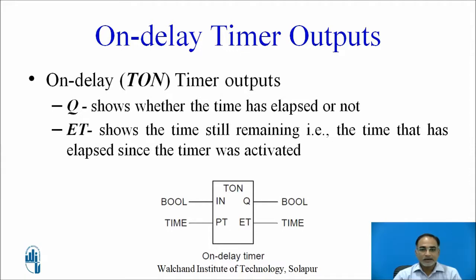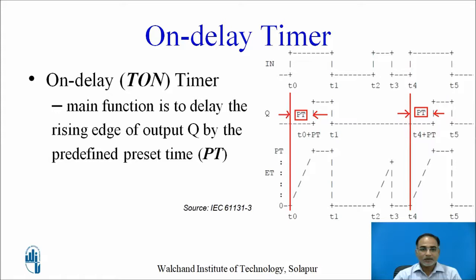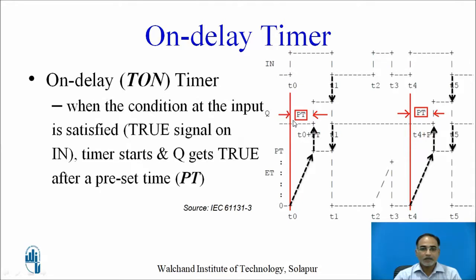The main function of the on-delay timer, also known as TON, is to delay the rising edge of Q by the predefined preset time. At t0, when the input changes from 0 to 1, the timer starts immediately and the ET value increments toward PT. When ET equals PT, Q changes from 0 to 1. The difference between the rising edge of input and the rising edge of Q is the PT duration.